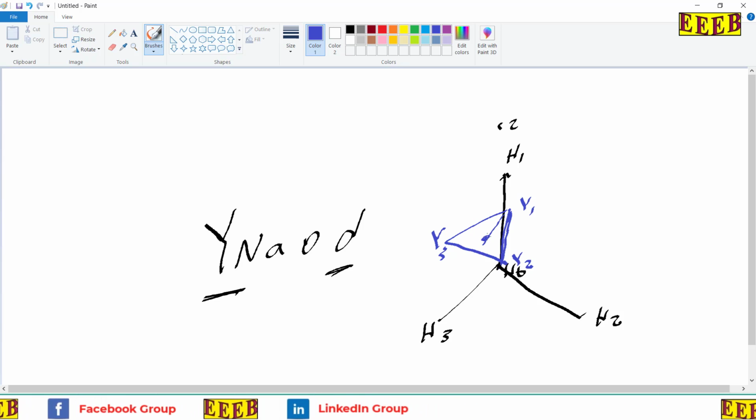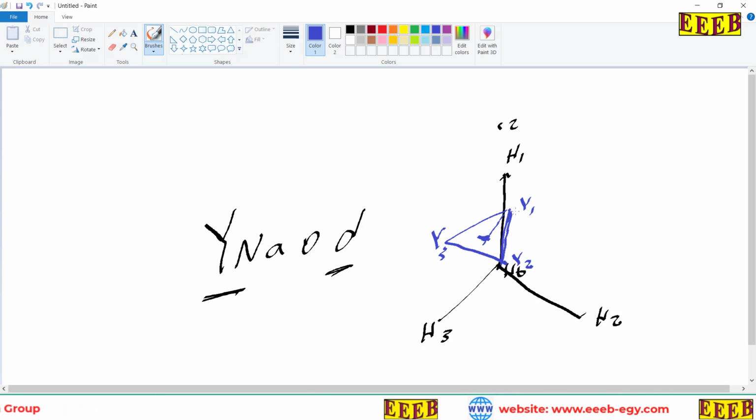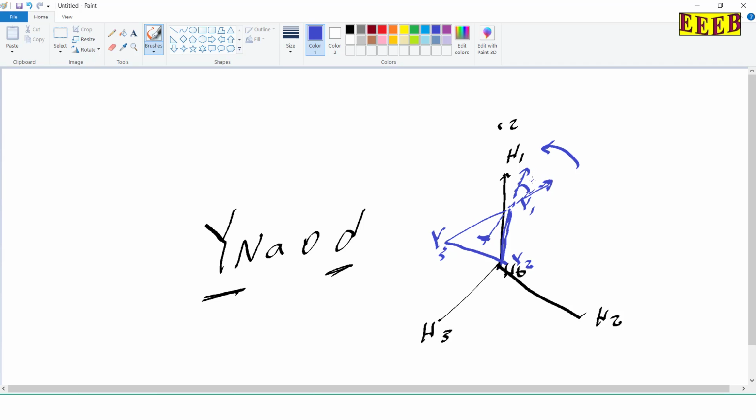So we can find the phase voltage between Y1 and the ground, it will be like this, because now this is line voltage and here phase voltage. So the line voltage is leading the phase voltage by 30 degrees. We can find that the tertiary phase voltage is pointing at clock number 1. So this transformer is YNa0d1, and the tertiary will be D1. So this is about the vector group.